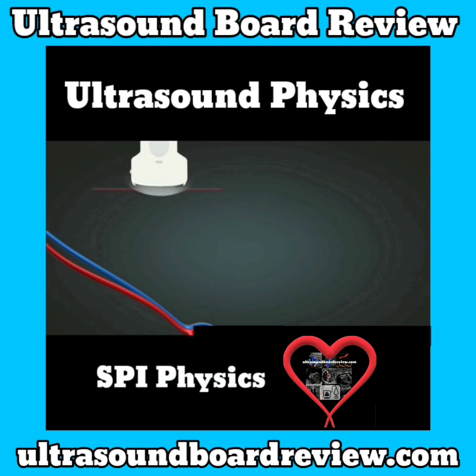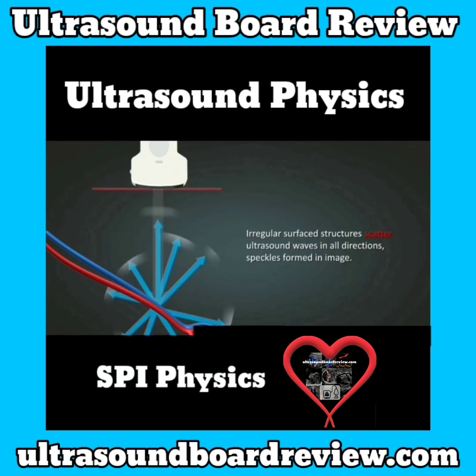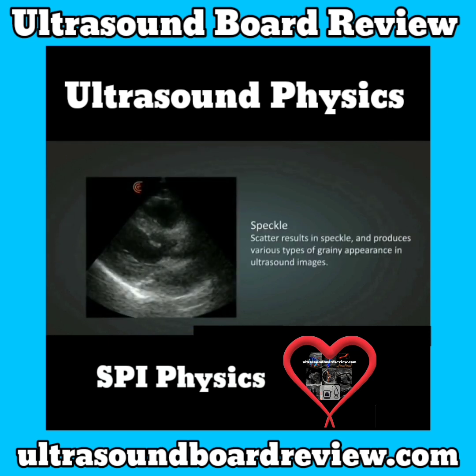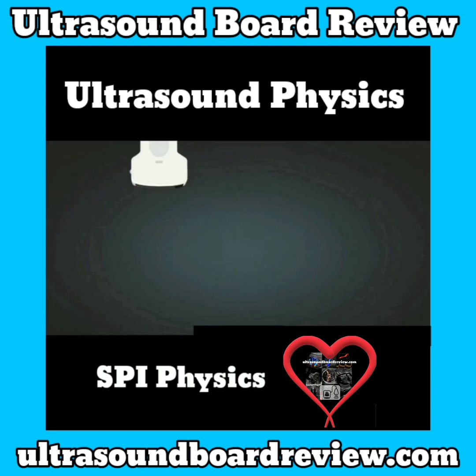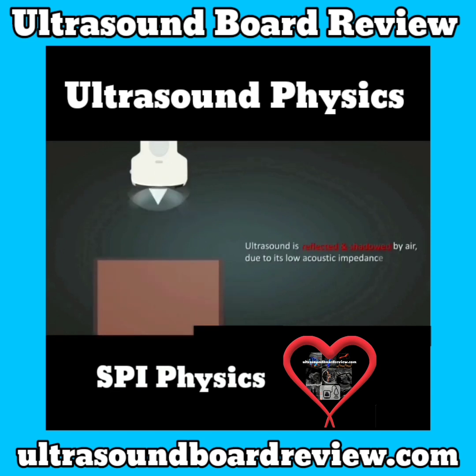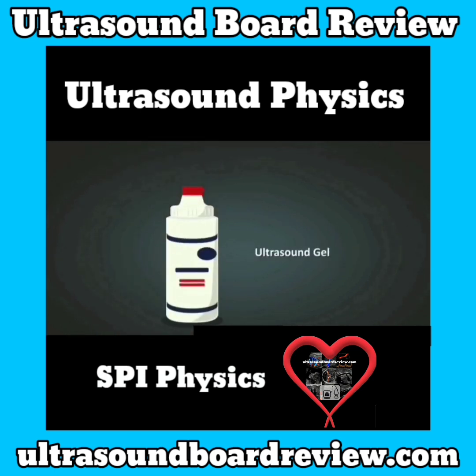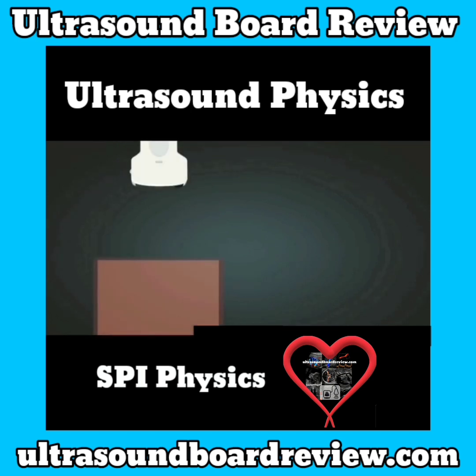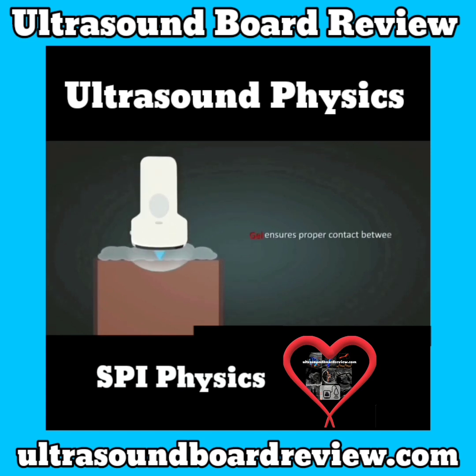Scatter occurs when ultrasound waves encounter a medium with a non-homogeneous surface. A portion of the sound wave is scattered in random directions. The consequence of scatter is known as speckle, which produces the grainy appearance in an ultrasound image. For sound to travel through the body, the medium must be acoustically coupled. Since ultrasound is reflected by air, we need to use gel, and there has to be proper contact between the transducer and the patient. When air is trapped between the transducer face and the skin, it reflects sound waves and creates shadowing.